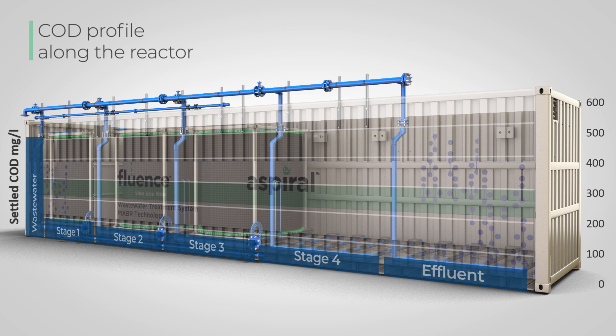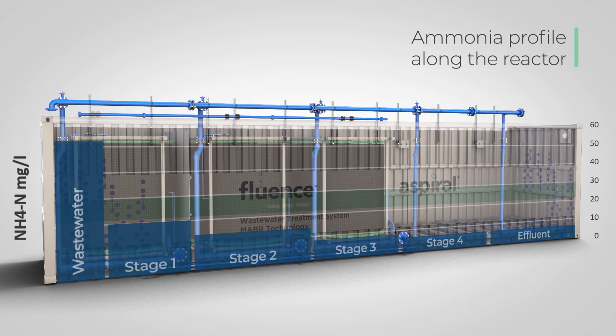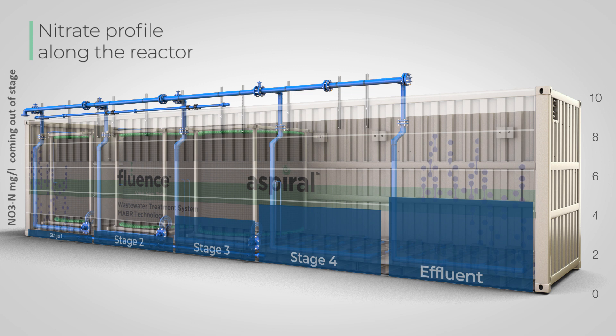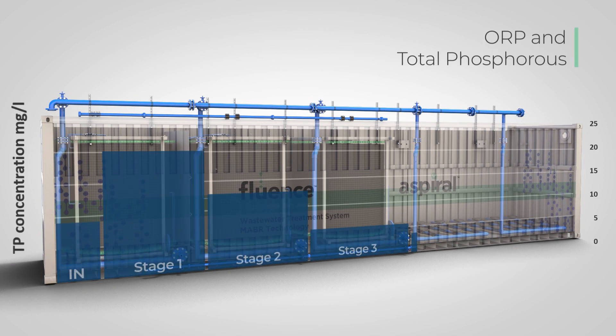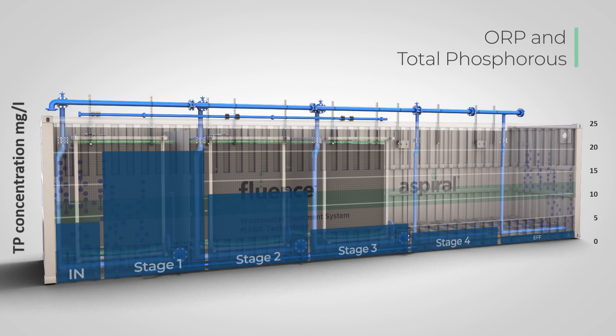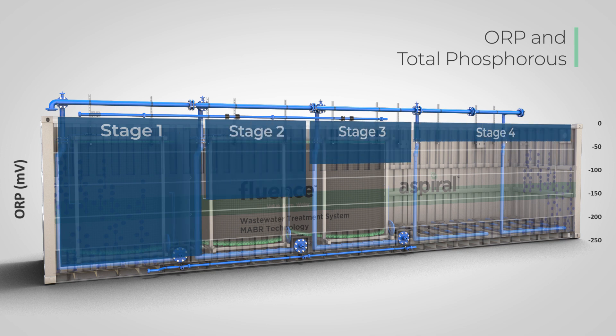The absence of dissolved COD enables the development of a nitrifying biofilm on the MABR membrane. Ammonia is nitrified at a decreasing rate by the biofilm. Nitrate concentration is close to zero coming out of the first stage, indicating full denitrification; subsequently, nitrate gradually accumulates to effluent concentrations of a few ppm. ORP conditions in the first stage are sufficiently low to support subsequent quantitative biological phosphorous removal of up to 90%.